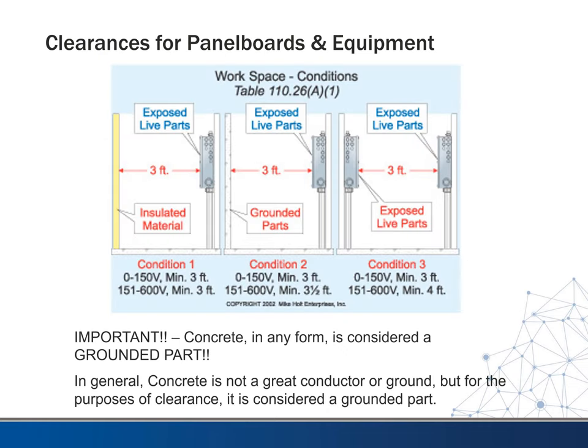One last thing we want to look at in terms of gear is that there are some requirements for clearances that we have to observe. These are defined in the National Electrical Code in Table 110.26(A)(1). They give three conditions. Condition one is you have exposed live parts and insulated material. Condition two is you have exposed live parts and grounded parts or material on the other side. And finally, you have exposed live parts with potentially exposed live parts on the other side. So if you're working on this one, you could have exposed parts at your back. Depending on the voltage you're dealing with, anything up to 150 volts, it's always 3 feet. We want 3 feet clearance.